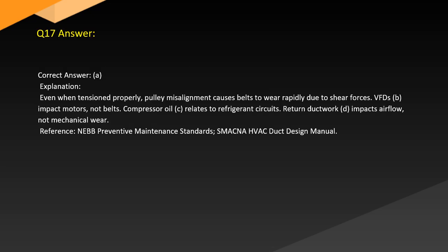Answer. Correct answer: A. Explanation: Even when tensioned properly, pulley misalignment causes belts to wear rapidly due to shear force. VFDs, B, impact motors, not belts. Compressor oil, C, relates to refrigerant circuits. Return ductwork, D, impacts airflow, not mechanical wear. Reference NEBB Preventive Maintenance Standards and the SMACNA HVAC Duct Design Manual.